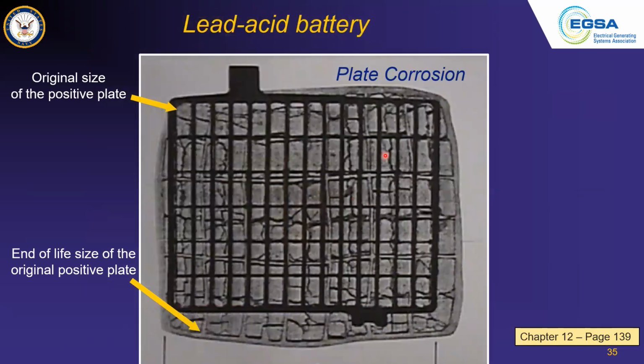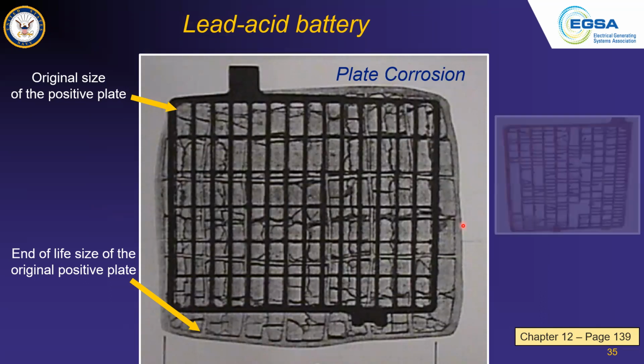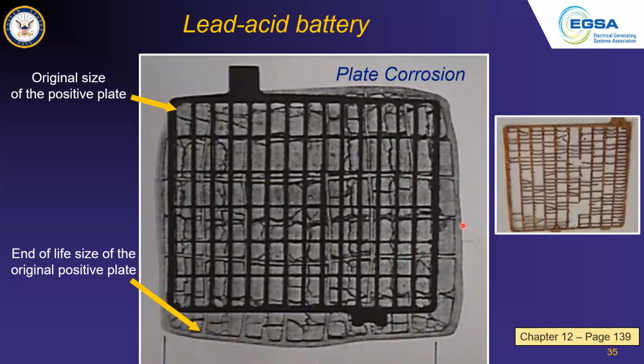With the effect of lead moving on and off these plates, this grid is going to expand. The darker shadow here is the original size, and it's going to expand to about 1.3 to 1.5 times its original size. In doing so, it's going to break some of this grid, so that's going to cause the battery to fail as well.